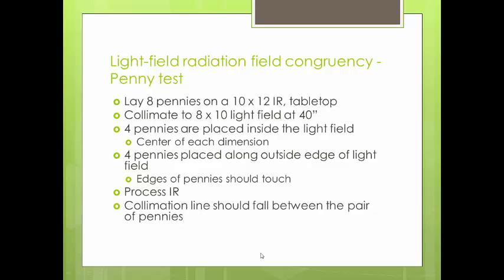The edges of your pennies should touch each other. Expose and process your IR, and you should see that your collimation line will fall between the pair of pennies.